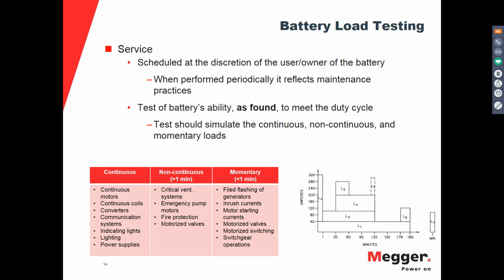So no previous maintenance, no previous preparation procedure, and the test has to be performed with the duty cycle. The idea is to profile the load to mimic the actual duty cycle of the battery, or as close as possible. In this slide, we're seeing a typical profile. This is an image from the actual IEEE 485 that specifies how to calculate or size the battery, and this is an example they have there for a load profile.